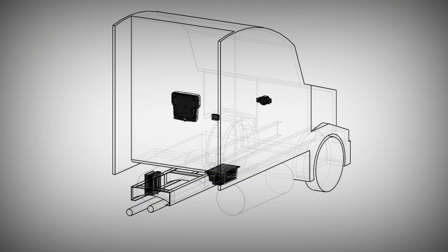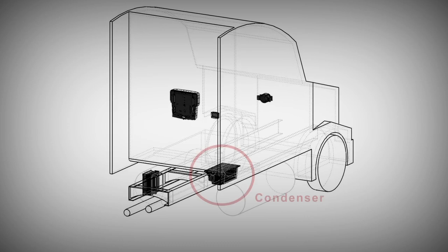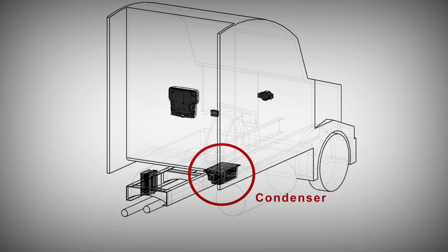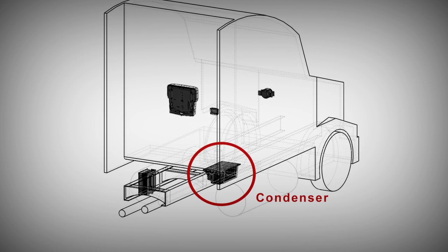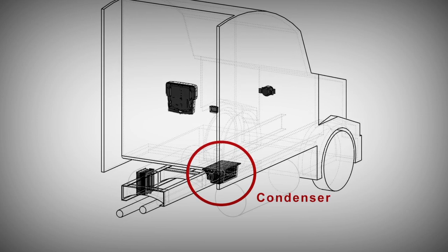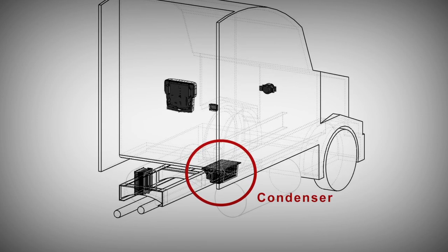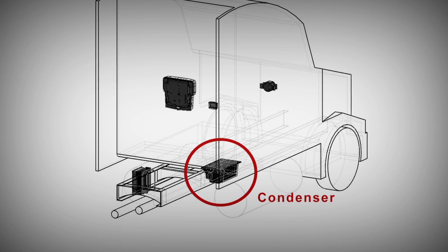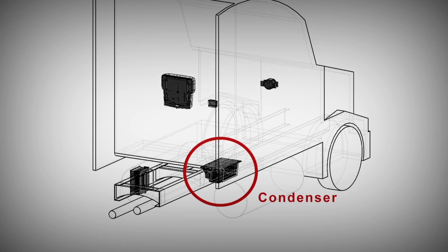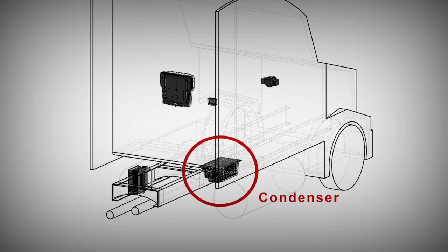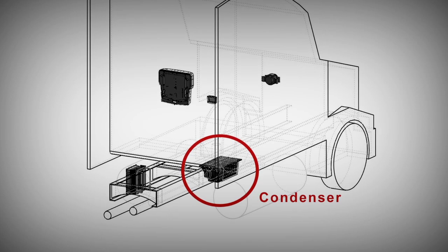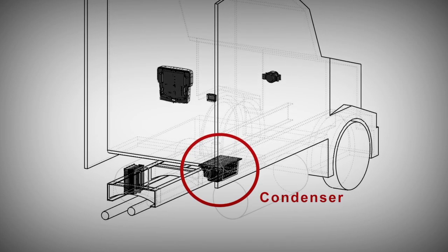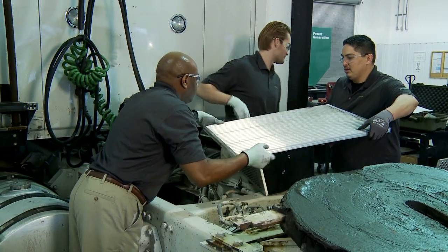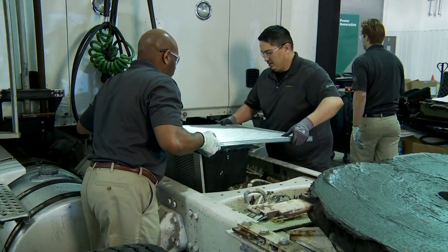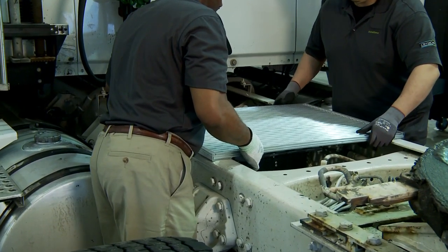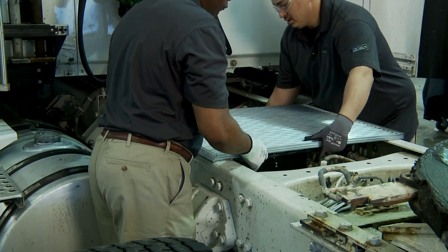To install the ClimaCab truck-mounted condenser, first determine an optimal location. Keep in mind that hose and harness connections should be oriented towards the rear of the truck, and extensions might be needed if the unit is located towards the front of the vehicle. Generally, locating the condenser at the rear of the sleeper, outboard of the frame and over the fuel tanks, is preferred if cab suspension clearance allows. Often, locating a deck plate mounted condenser between the frame rails above the drive shaft support bearing is an alternative.